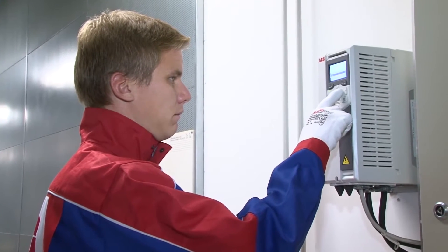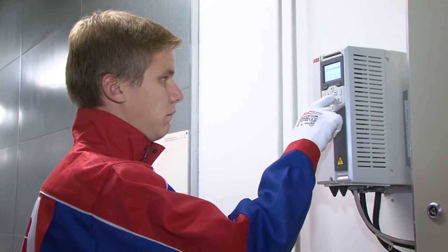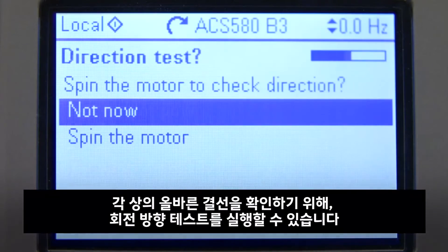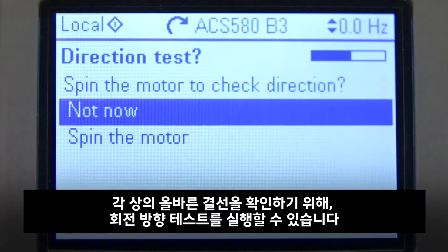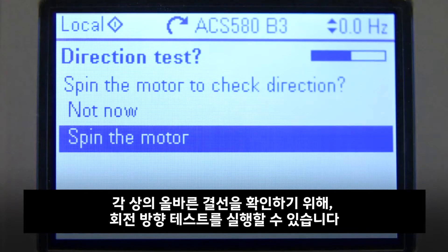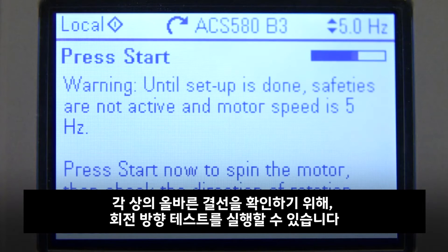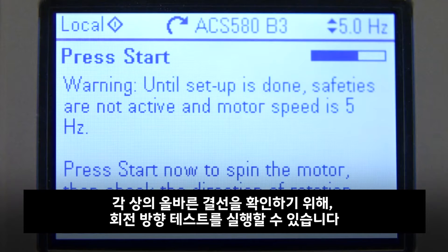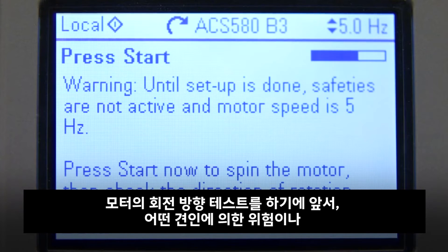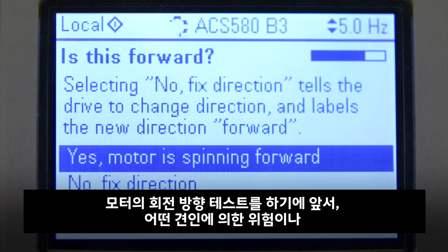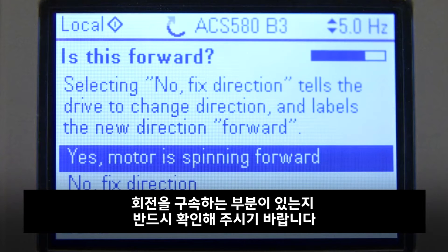After the motor values are set, a direction test can be run to determine that the phases are connected in the right order. To do this, ensure that the motor can rotate freely without causing any life-threatening situations or breaking parts of the system.